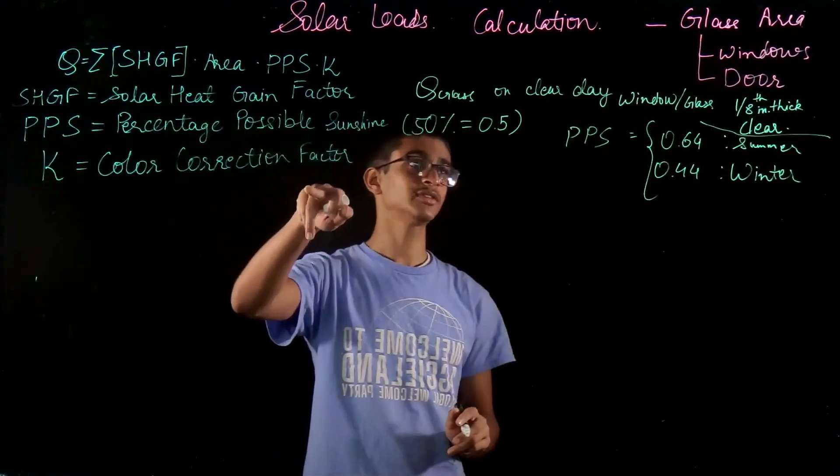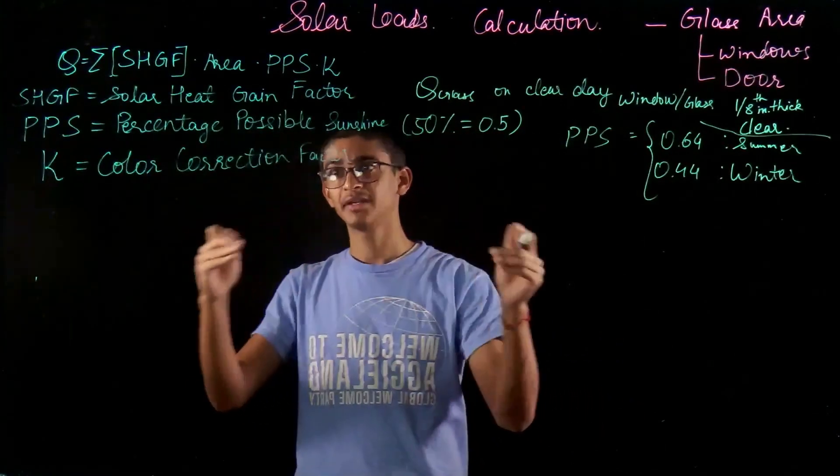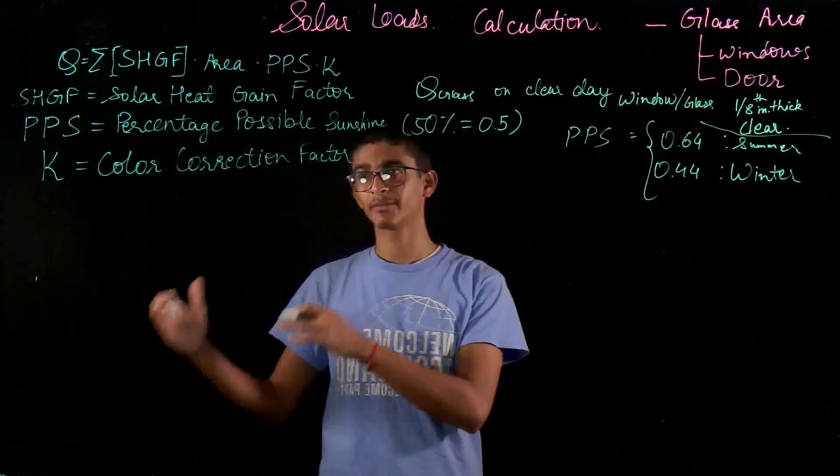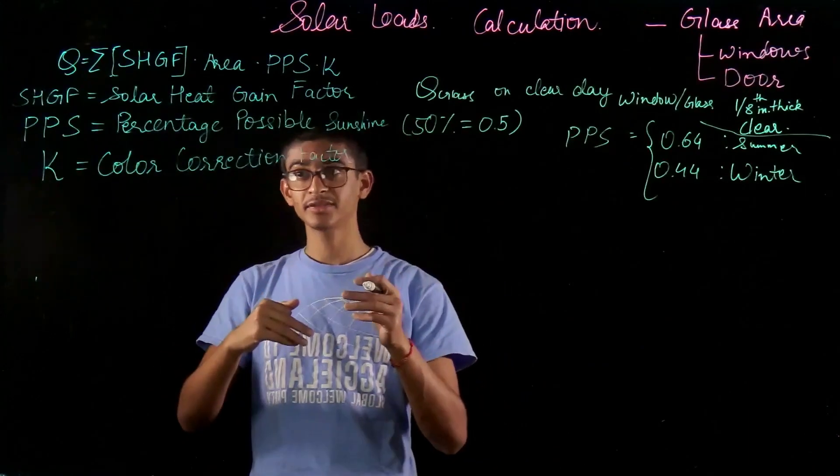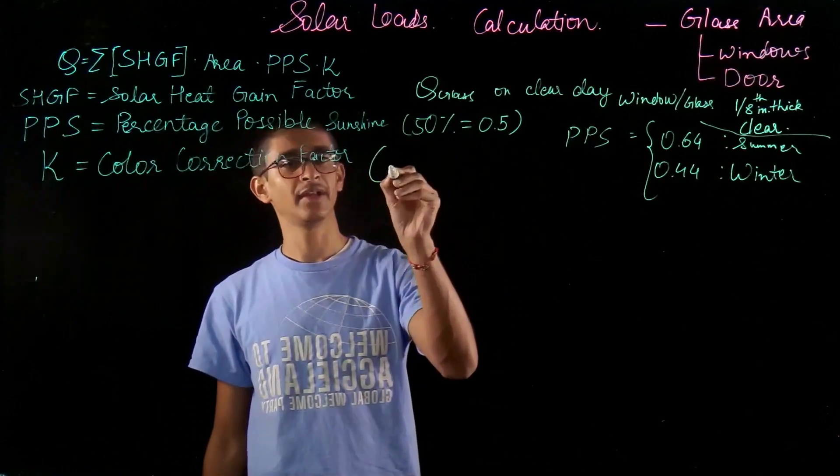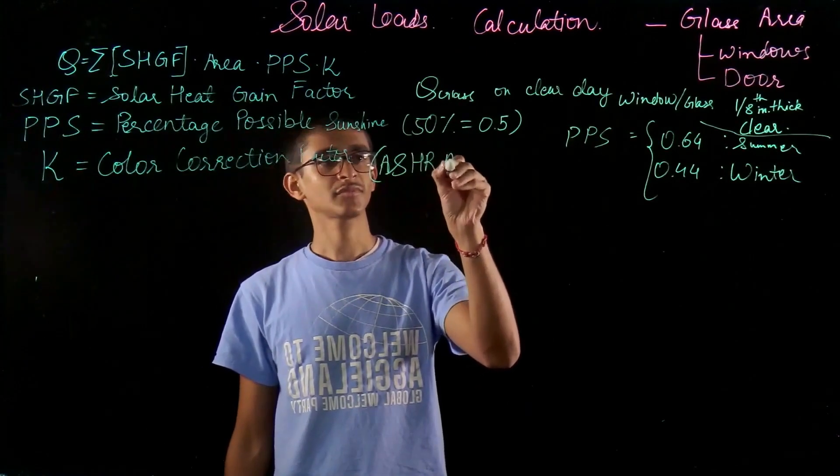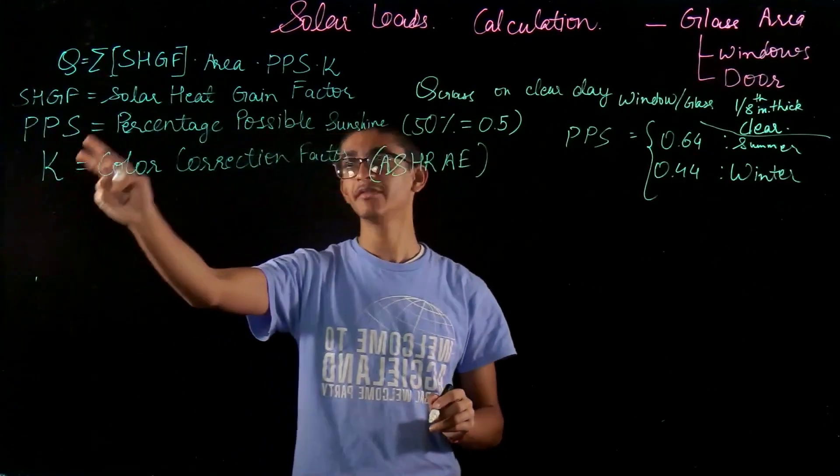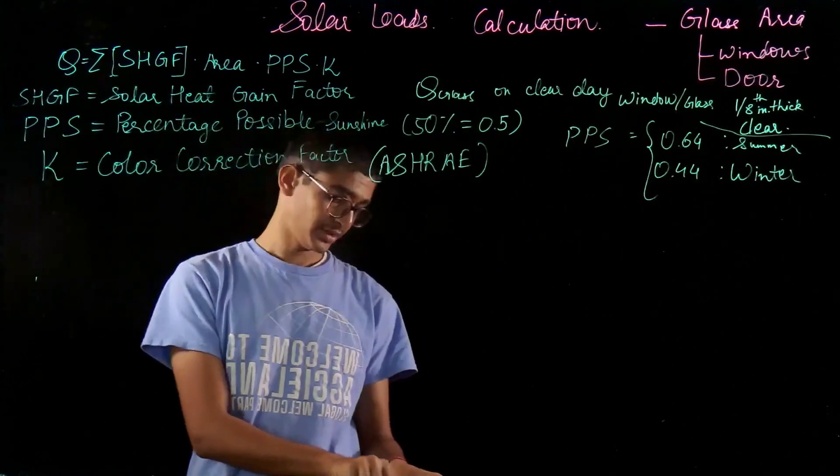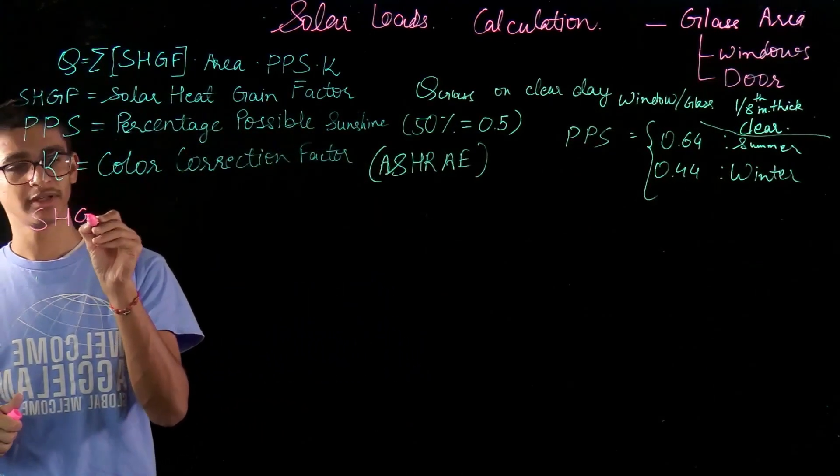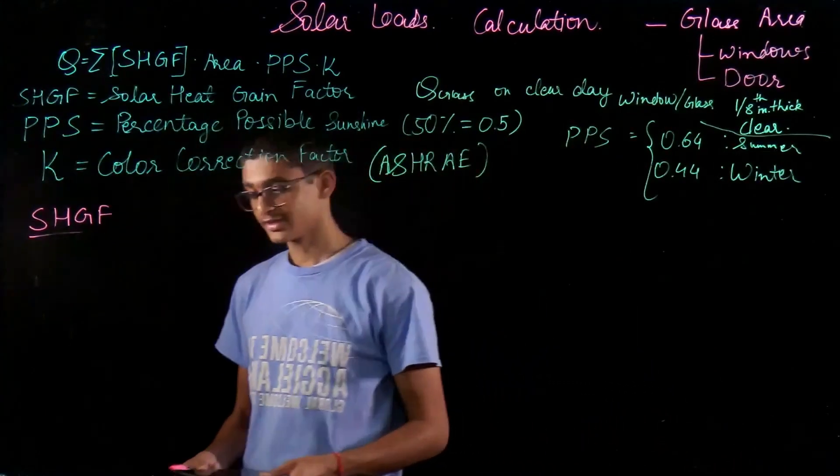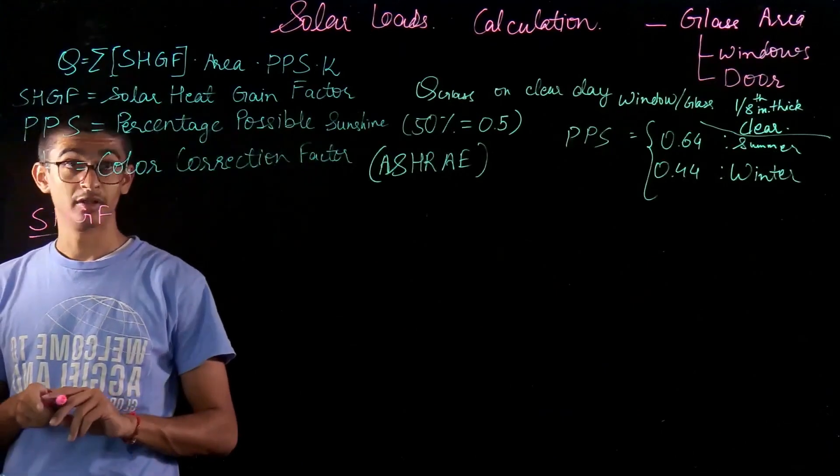K is the color correction factor that comes into account because if we have a black object inside our room, it is going to absorb more heat. If it is a white object, white colored on the surface, it is going to absorb less heat. That will take into account the different colors of our objects inside the room, the furniture, sofa set, everything. This K value will take into account those things. These values are also available in ASHRAE charts. For SHGF and K, we need to look at the ASHRAE charts.